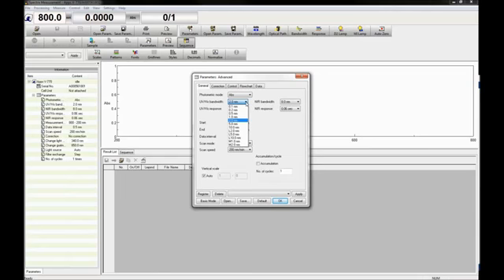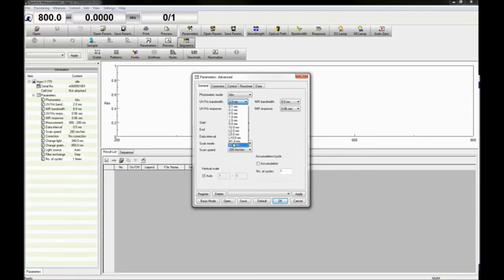Different beam shapes are also available. L is a low stray light mode and decreases the width of the beam shape, while M can be used for microcells.